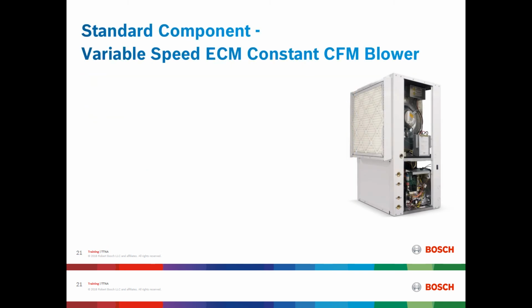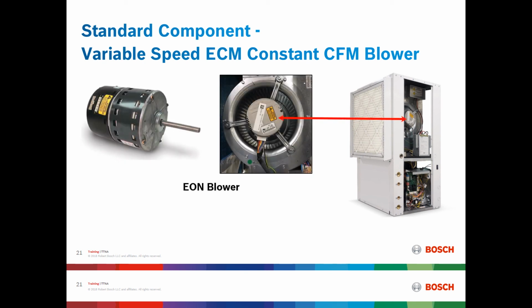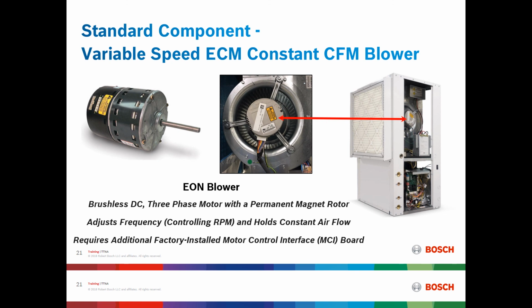The blower, as mentioned in the SM-Rev-V, is a variable speed electronically commutated constant CFM blower. This blower is referred to in the industry as an ECM. It is a brushless DC 3-phase motor with a permanent magnet rotor. It adjusts frequency, thereby controlling revolutions per minute, and holds constant CFM or airflow at approximately 400 CFM per ton of cooling. It does require an additional factory-installed motor control interface board.